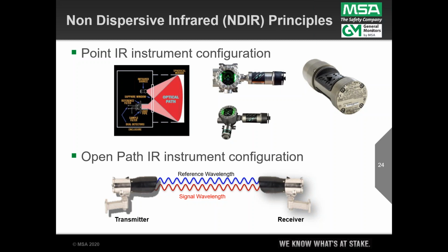And what's the benefit here? This thing sees a gas leak that your point detectors very well may have missed, because again, point detector depends on impingement. This guy, you got a 100-meter basically light fence line of light, and much greater opportunities to detect the gas.